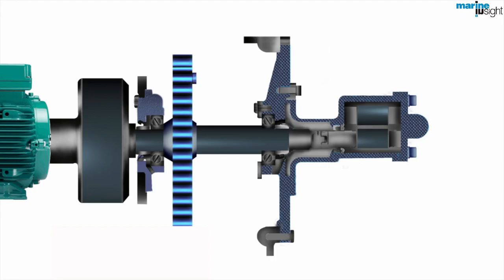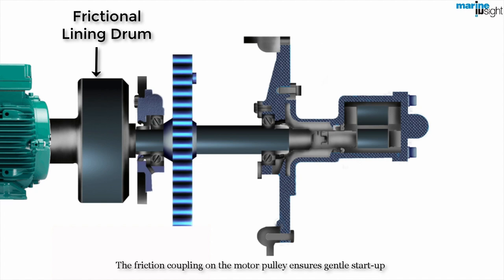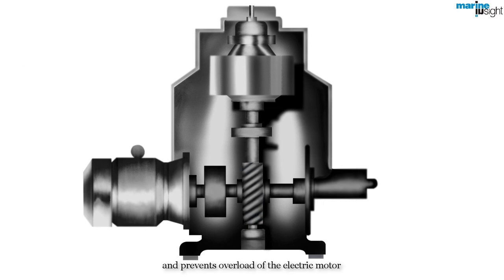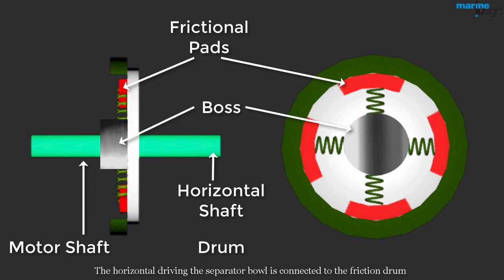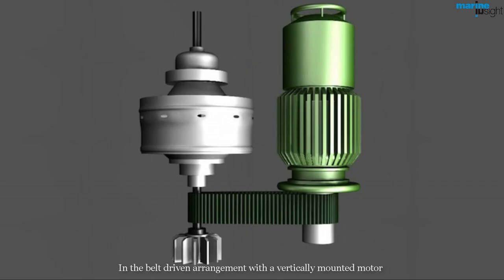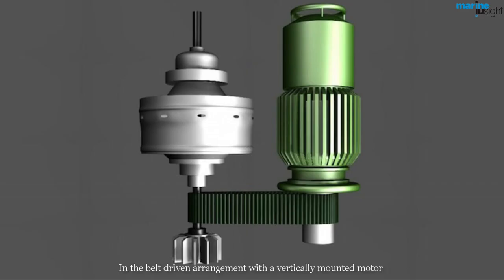The friction coupling on the motor pulley ensures gentle start-up and prevents overload of the electric motor. In the shaft-driven separator, the motor shaft is connected to the boss, which carries the frictional lining pads. The horizontal shaft driving the separator bowl is connected to the frictional clutch drum. In the belt-driven arrangement with the vertically mounted motor, the frictional drum is provided on the motor shaft, which carries the belt to drive the vertical shaft of the separator.